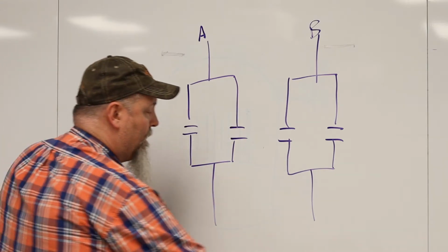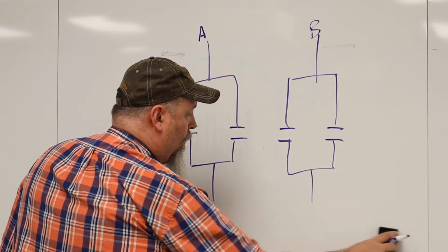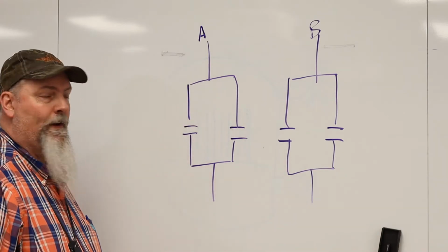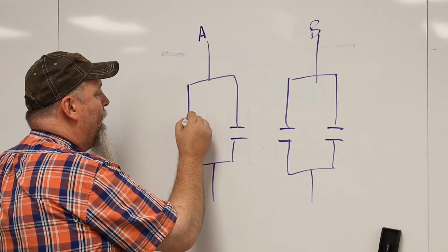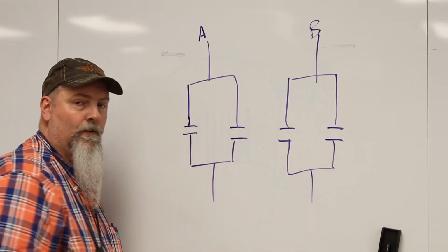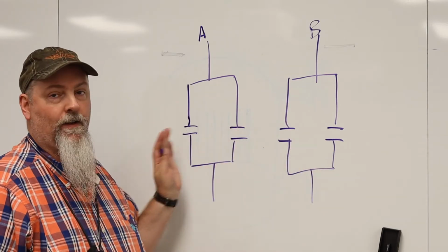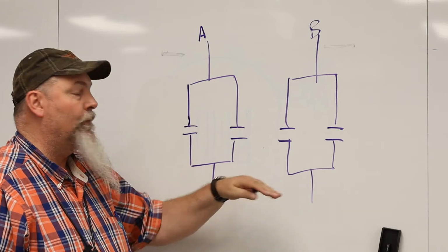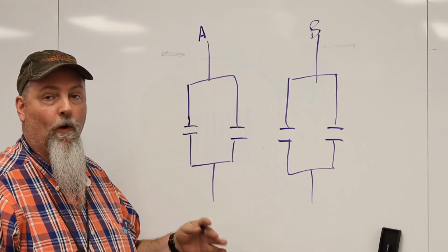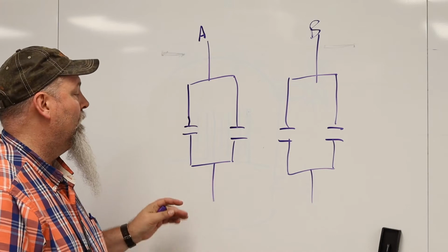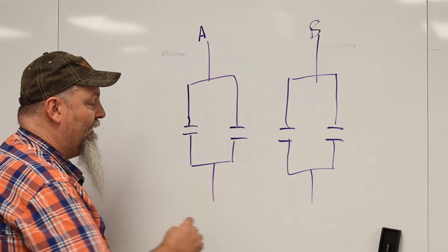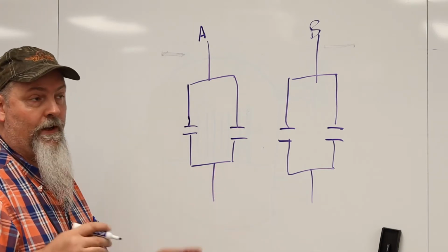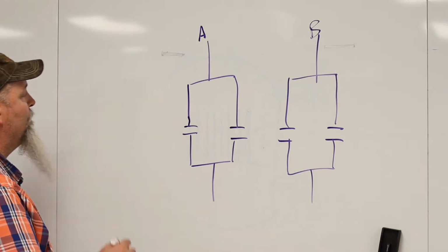Now in this logic, what we need it to do is we need to say, hey, when we get some logic, maybe we need one of the four, maybe we need two of the four, what combination of two of the four, in order to send a signal to cause the isolation or the scram to happen.